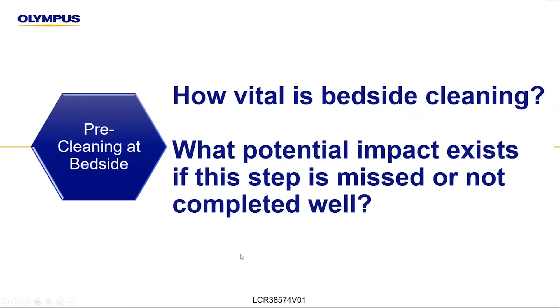And the impact, if it's not done properly or not done at all, is that it basically makes the manual cleaning step much more difficult and increases the risk that the manual cleaning may not be done adequately. And that has downstream implications in terms of the ability of organisms to survive the high-level disinfection. And if we can go to the next slide, I wanted to put together a little bit of data. So it's not just me talking about publications that are out there.